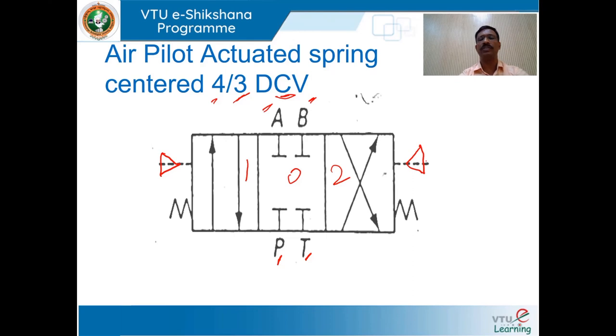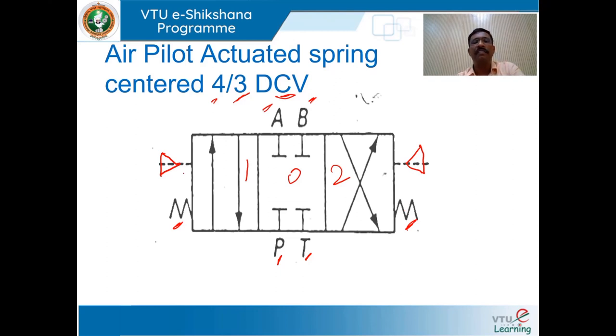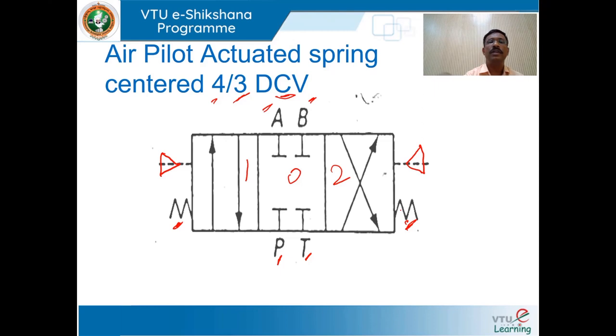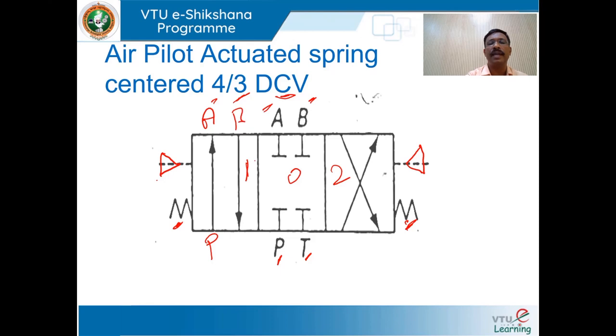When the valve is not actuated by an air signal, opposing spring forces move the valve to the center path configuration. When the spool receives an air signal on one side, the valve shifts to position 1 — P connects with A and B connects with T.